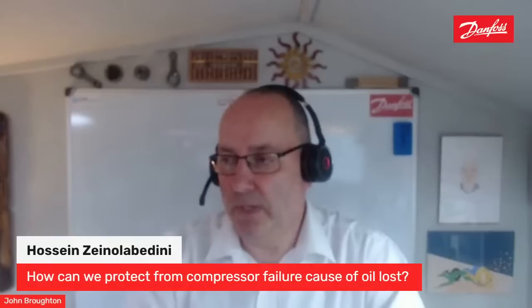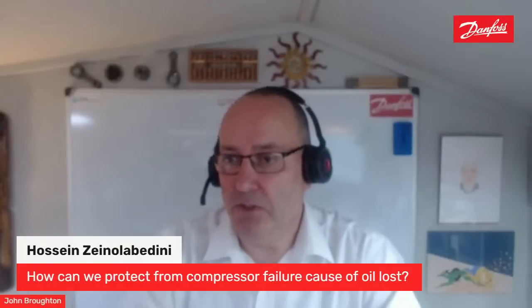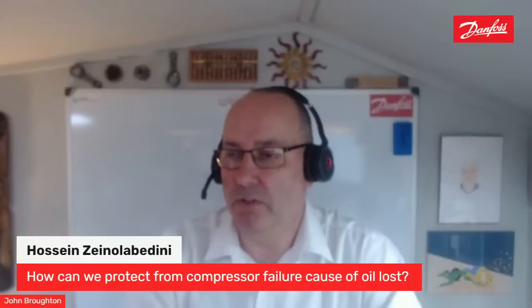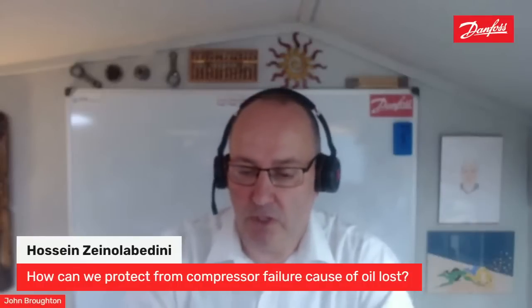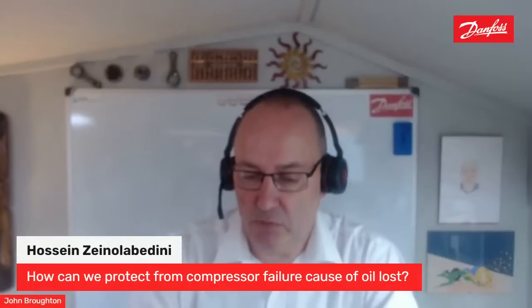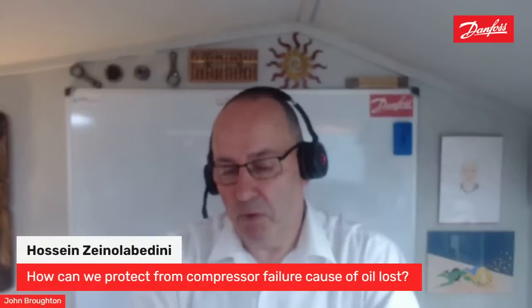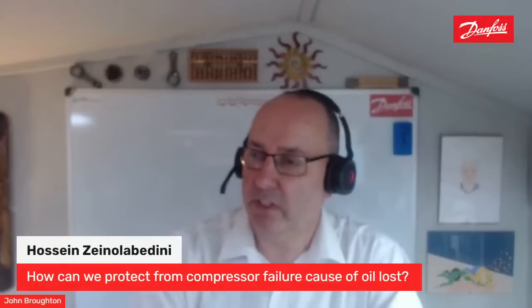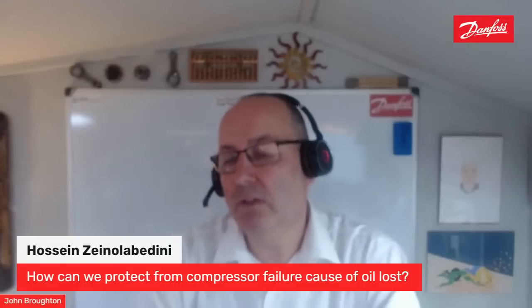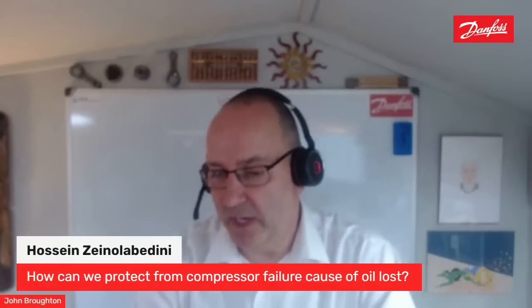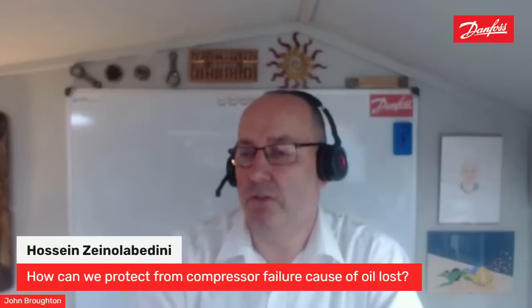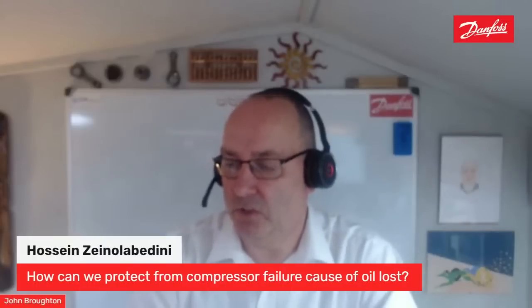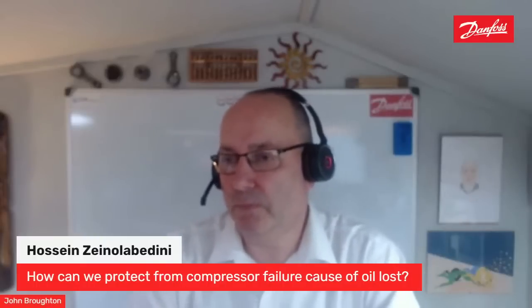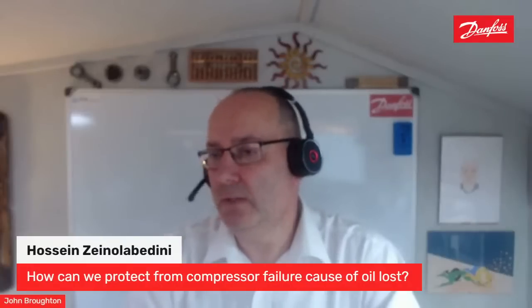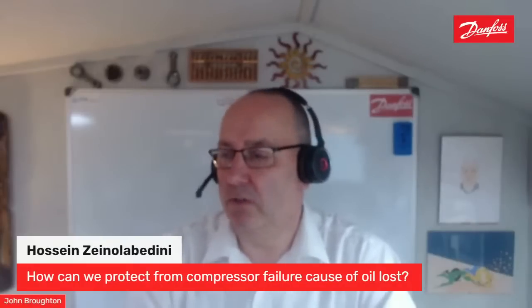The other thing is commissioning, and I come back to this phrase quite a lot. When you start a new installation, commission it, run it up, make sure it's working. Then maybe five days' time, come back and check the oil level. Is the oil level okay? If it's not, top up the oil level. Come back a little bit later, how's the oil level? Just keep a check on it for the first few weeks of that installation to make sure that it's not carrying over too much oil. So, hope that answers that question, Hossein, in a fairly simple way.